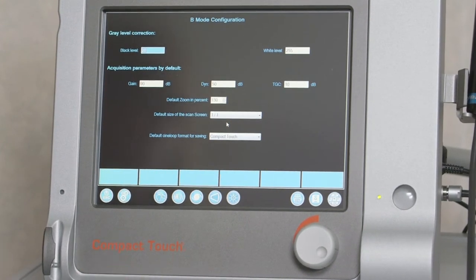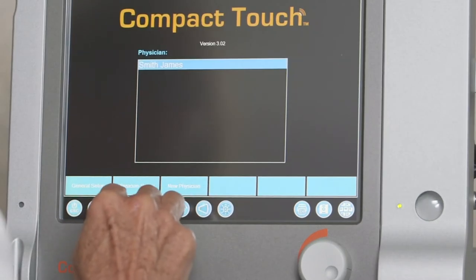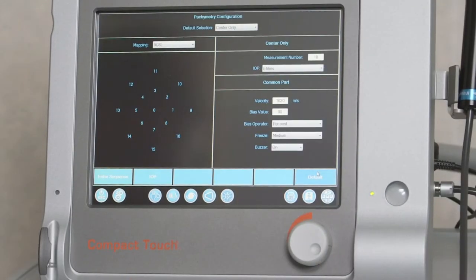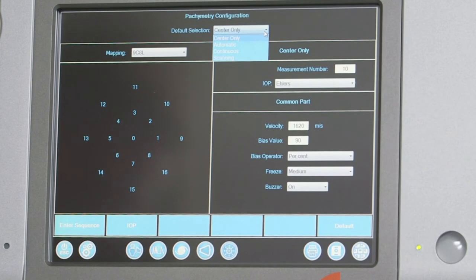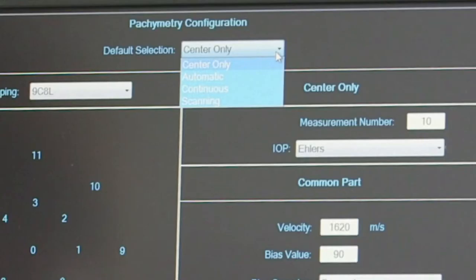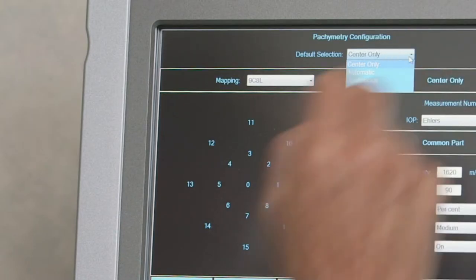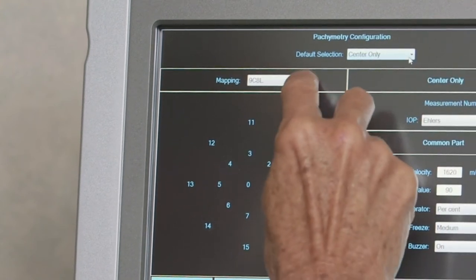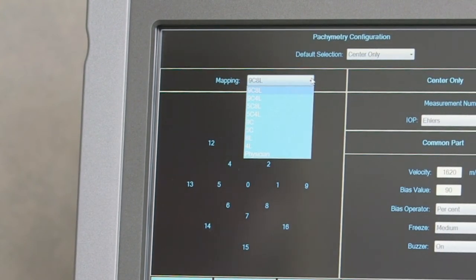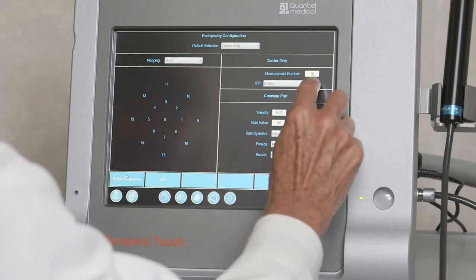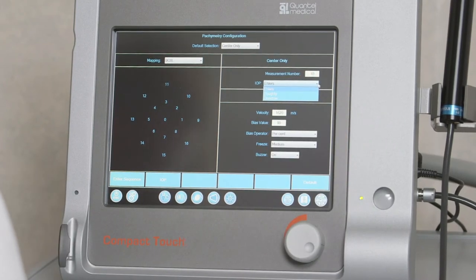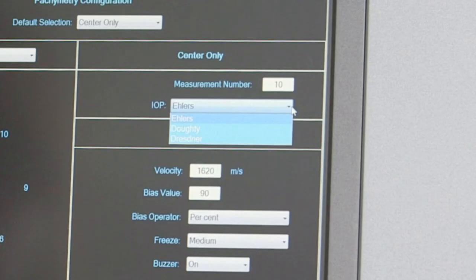Selecting Pachymetry Setup opens the Pachymetry Configuration screen. The Default Selection field allows the examiner to specify the default layout of the Pachymetry Acquisition screen. Four acquisition modes are available – Center Only, Automatic, Continuous, or Scanning. The examiner can also choose from eight predefined mapping sequences using the Mapping pull-down menu. Alternatively, a custom mapping sequence can be created by selecting Enter Sequence from the bottom toolbar. The Compact Touch software provides three correction tables for adjusting IOP – Ehlers, Doughty, and Dresdner – all of which can be viewed by selecting IOP on the right-hand side of the screen.